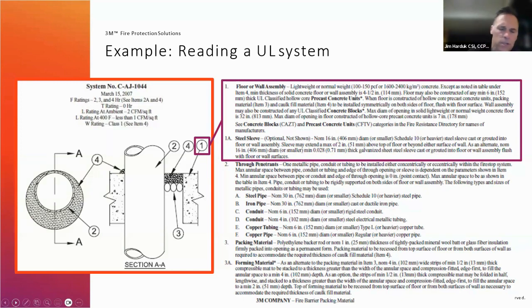And this particular drawing, I selected it because it allows for various types of through penetrating items. It allows for a steel pipe up to 30 inches, an iron pipe up to 30 inches. It allows for rigid steel conduit up to 6 inches, EMT up to 4 inches, copper pipe, and copper tubing. If you think back to the video where they had a group of different through penetrations that were all being tested at the same time. So it's not uncommon on a system drawing to find that there are numerous through penetrating items that are allowed to be used with that particular system.